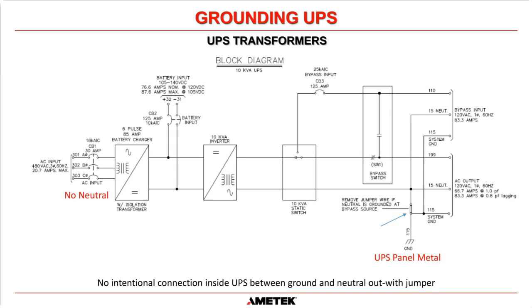So the reason why an AMETEK SCI UPS is considered a separately derived source is, as you can see here, there is an input transformer, and it is an isolation transformer. You can see there is no electrical connection on the primary side with respect to the secondary side. And you'll also notice that on our UPS systems, we do not run a neutral to the input to the battery charger. We usually take a 3-phase 480 delta supply from an MCC. And there's absolutely no need. In fact, we don't have anywhere to land a neutral inside our cabinets. So there is no neutral run into the charger input to our UPSs.